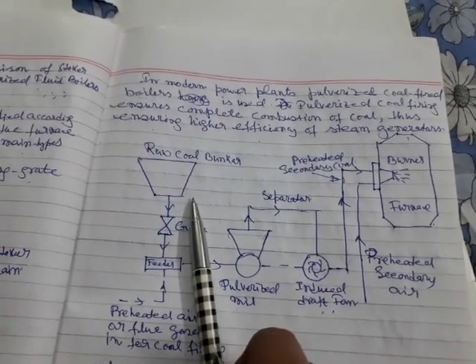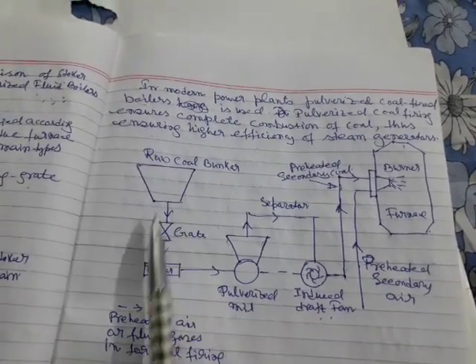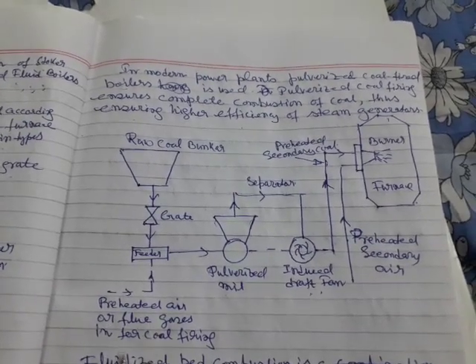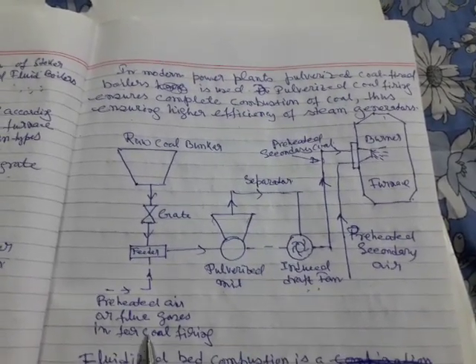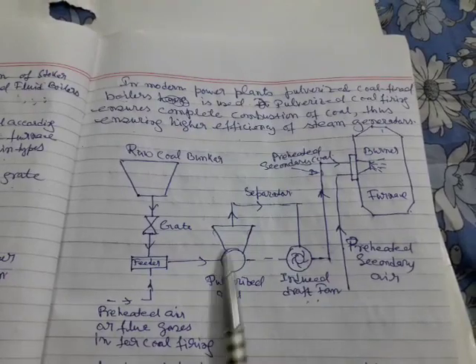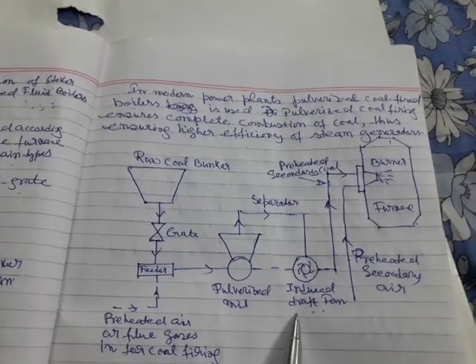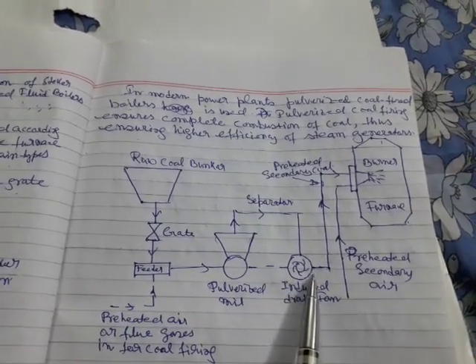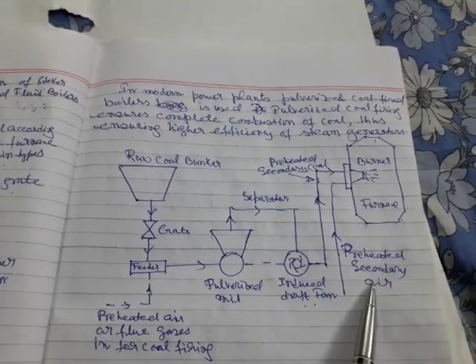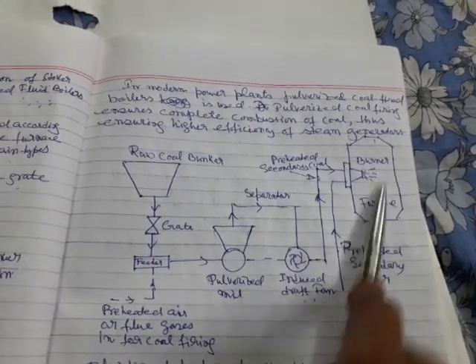In the schematic diagram of the pulverized coal fired boiler: raw coal enters from the bunker through a gate and feeder, preheated air from flue gas enters, and pulverizing takes place in the pulverized mill. After a separator, coal enters via an induced draught fan into the burner. Pulverized coal enters the burner along with preheated primary and secondary air, and burning takes place in the furnace.